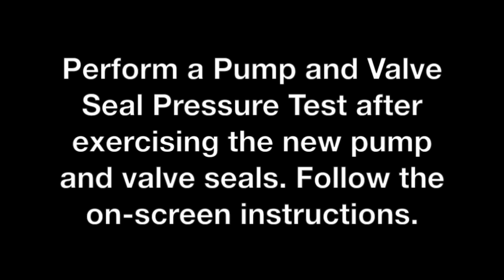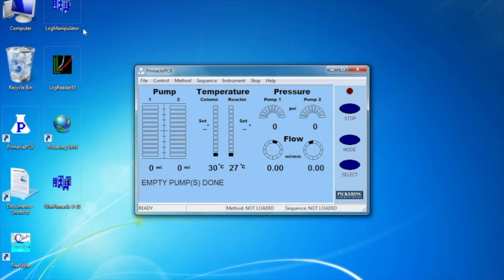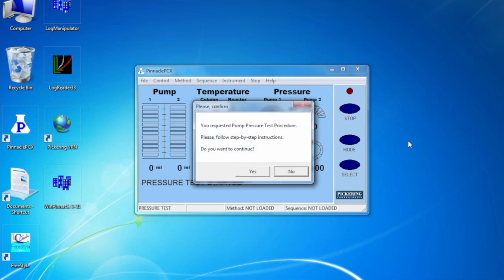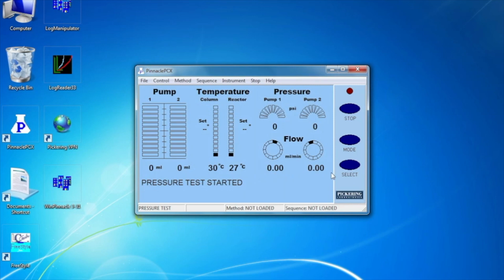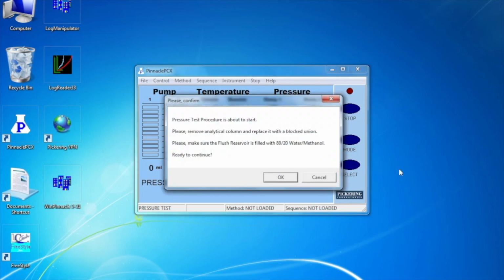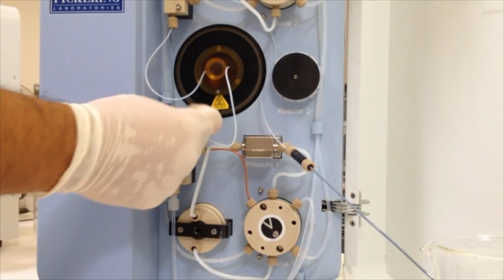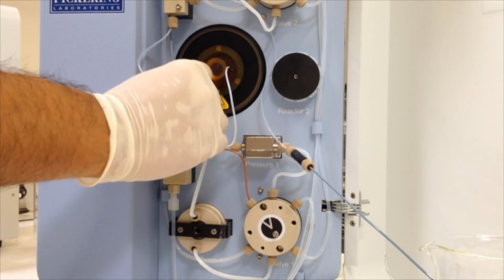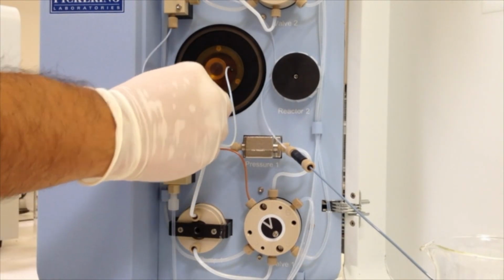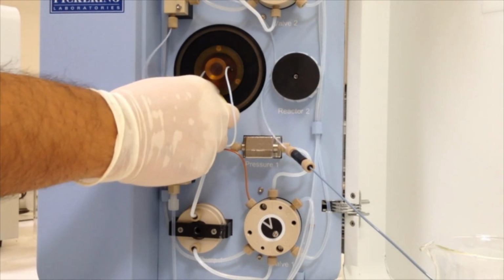Perform a pump and valve seal pressure test after exercising the new pump and valve seals. Follow the on-screen instructions. The pump and valve seal pressure test can be found in the Maintenance section of the Instrument drop-down menu. Remove the analytical column and replace it with a blocked union or a plug in the mixing tees. This will prevent any backflow onto the analytical column. Click Continue when this is complete.